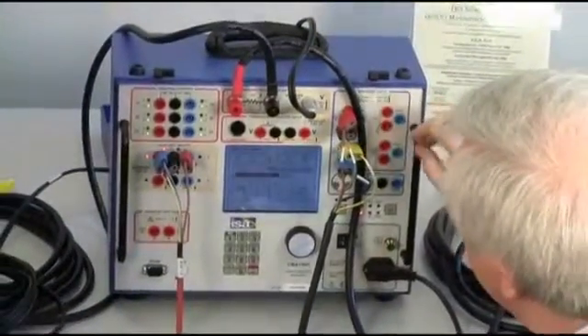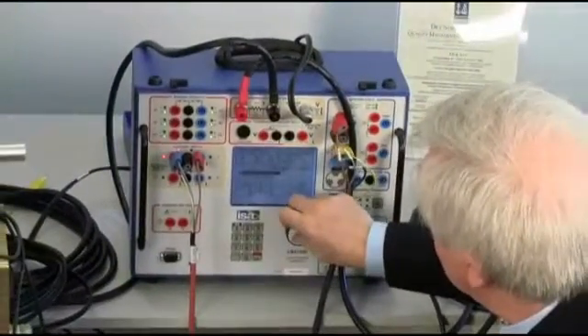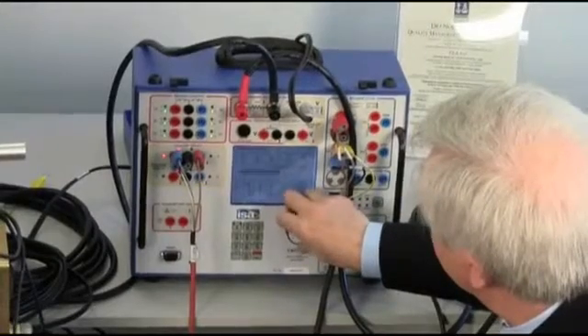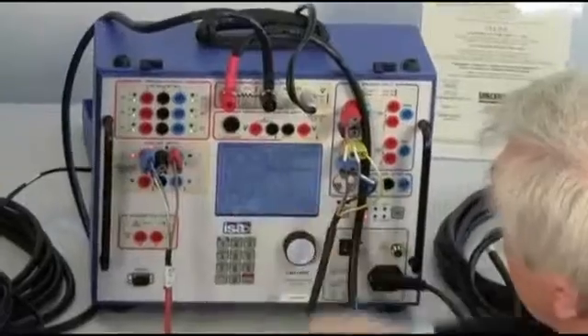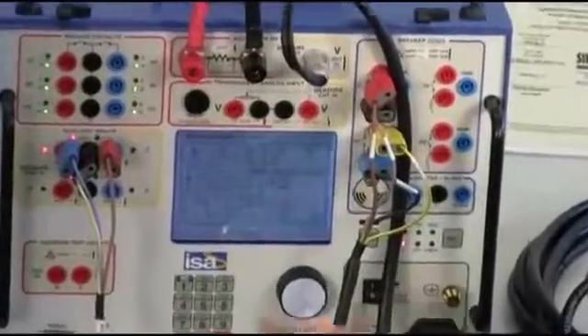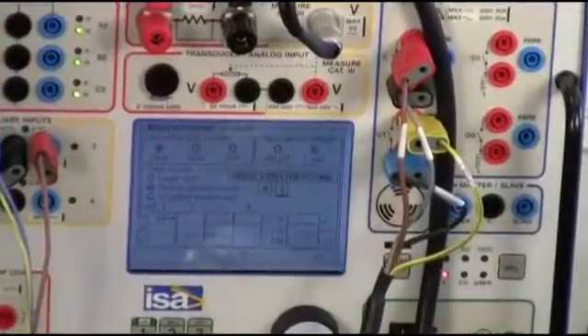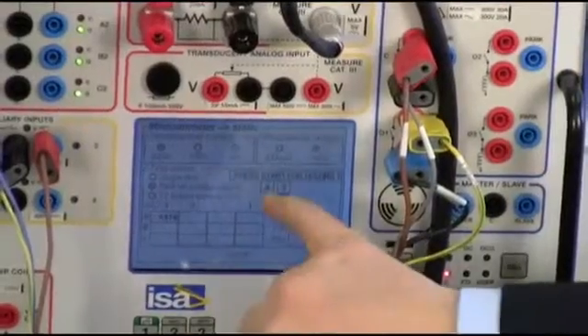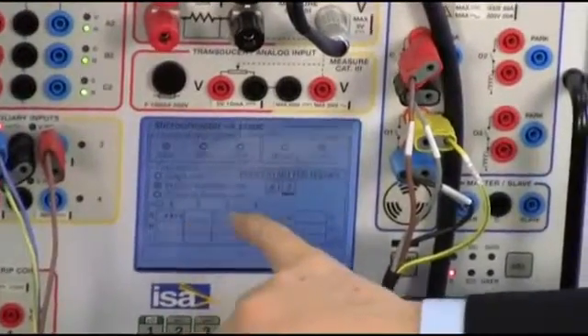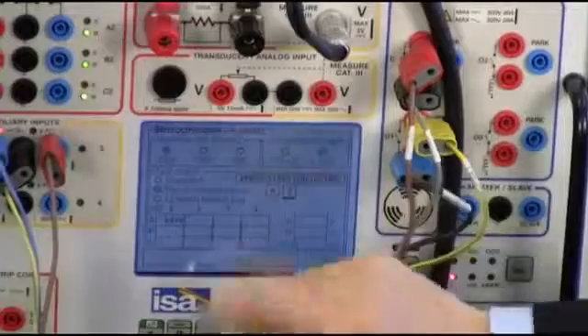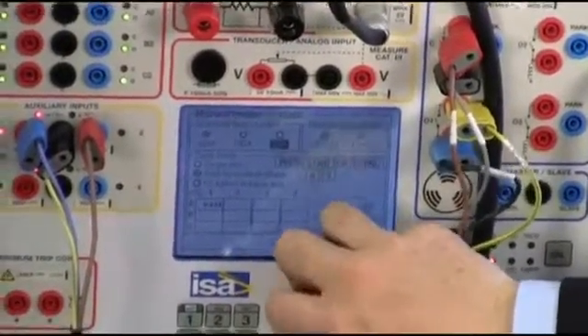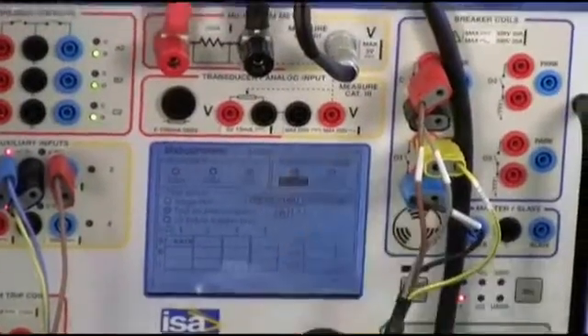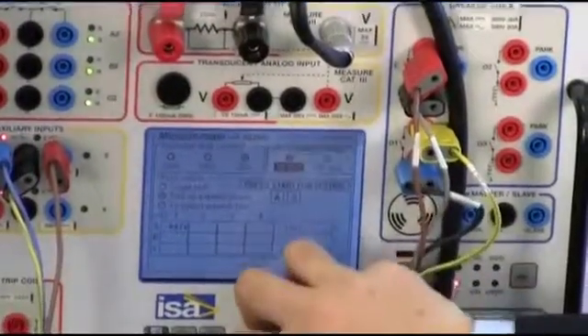Now, I want to show you that I actually have the same resistance value, injecting a much smaller current, that is, for instance, 20 amps. So I say that now I am testing A phase 2, contact 2. Then I come here, and I say 20 amps, with 10 milliohms range.